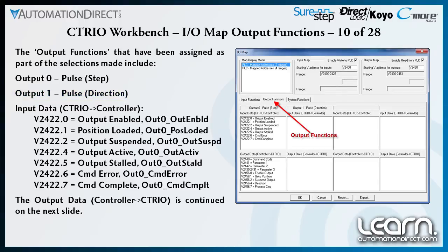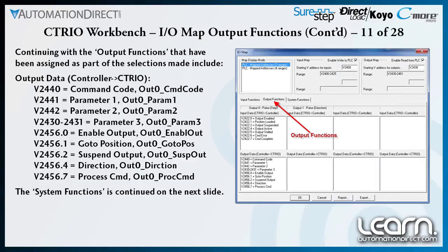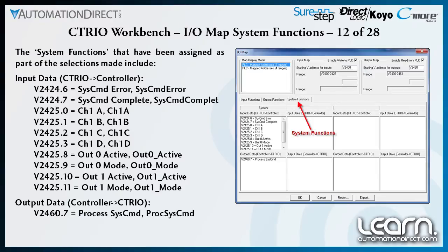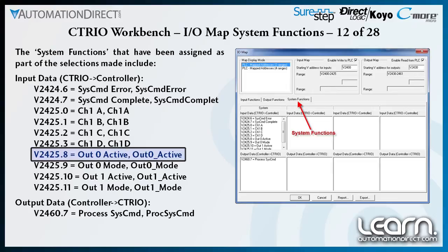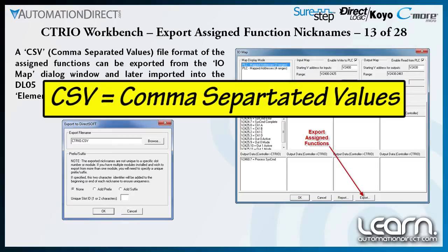Under input data are the various bit signals that the CTRIO communicates to the DL05 PLC controller. The system functions assigned can also be seen. I have used the bit signals in my ladder logic to indicate when channel 1 input terminal C, designated as V2425.2, is true for my homing signal, and I also used the output 0 active bit, designated as V2425.8, to indicate when a move is no longer active. As a time saver, I can export the assigned functions as a comma separated values file, type CSV, from the IOMAP dialog window.